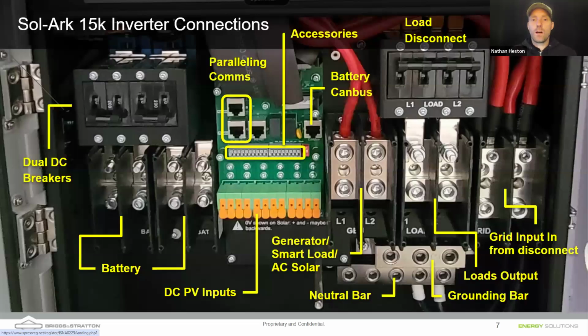The generator port here is shown on the left side of the screen. That's a port that has an 80 amp continuous maximum, so a little over 19 kilowatts. You could use that to bring in a generator. You could use that to bring in AC coupled solar, or you could use that as, my favorite method, a smart load output. So you can control the on off of a sub panel based on battery percentage with that.